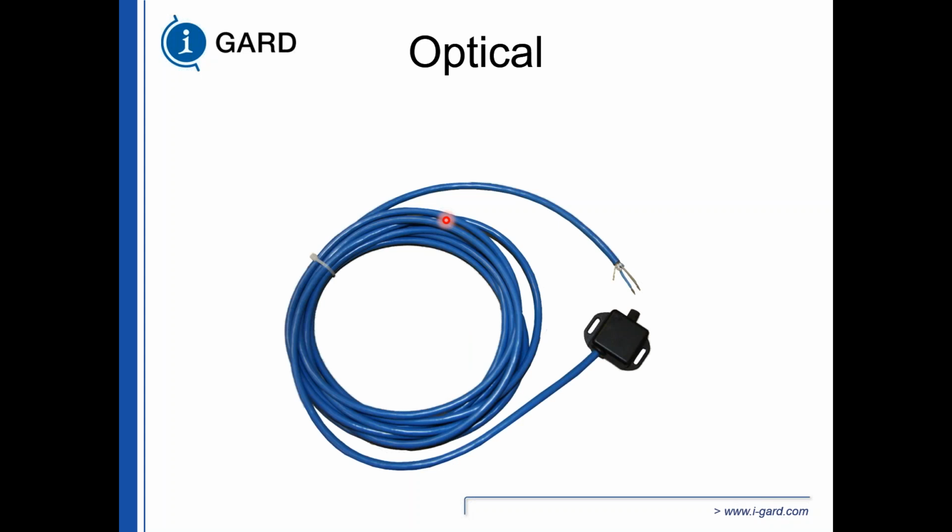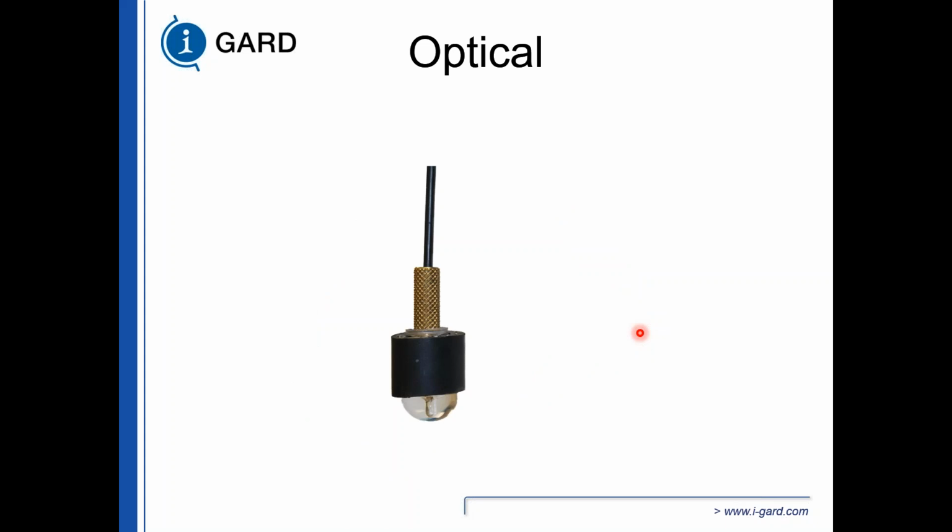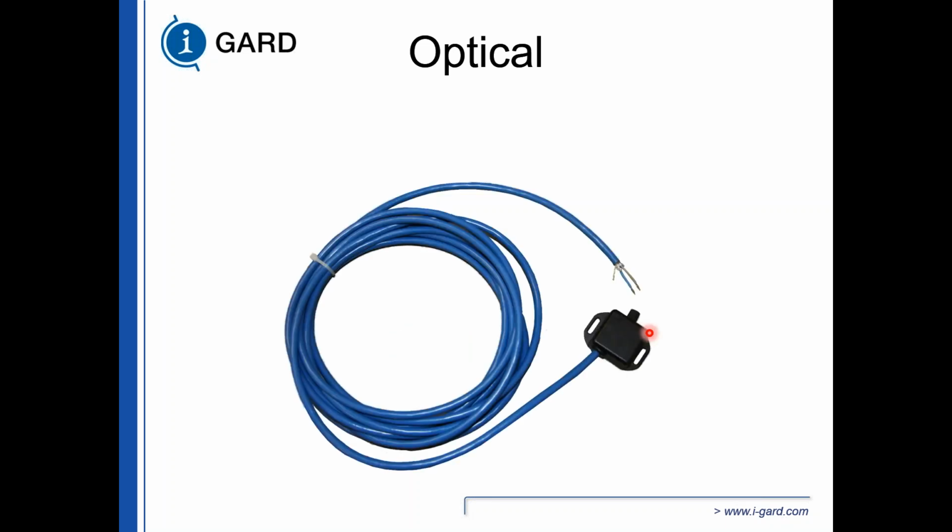Or we have the point sensors, which convert to a fiber input for shipping splits if you want to use the fiber. The fiber we have is either closed clad, which is what we have here, or open clad, when you don't have that black protective sleeving over the fiber, so you can wrap it around bus if you want and use this device to bring that signal back to the relay.